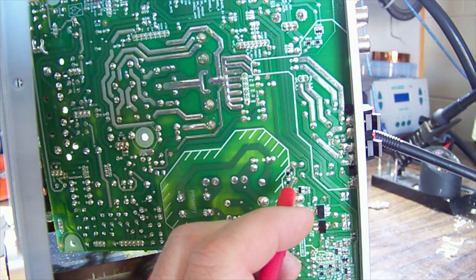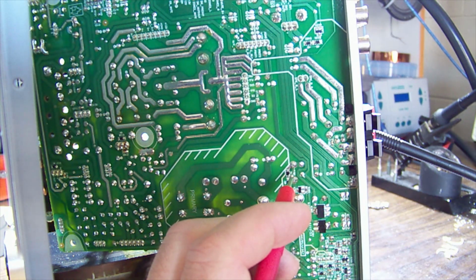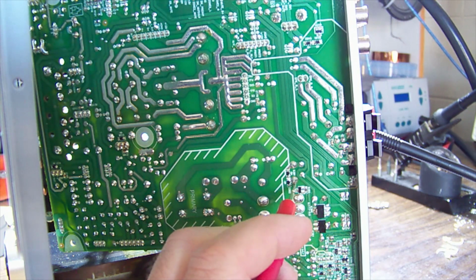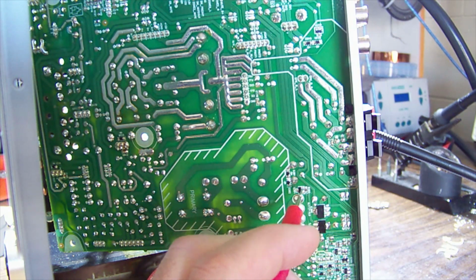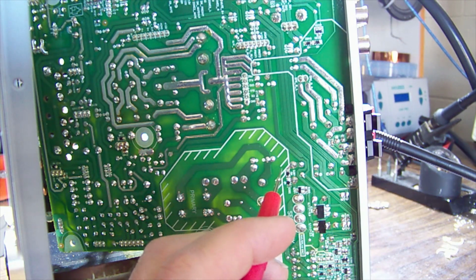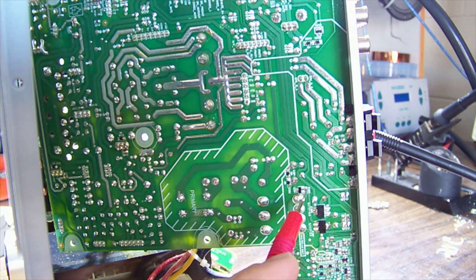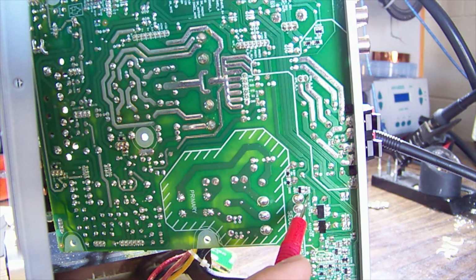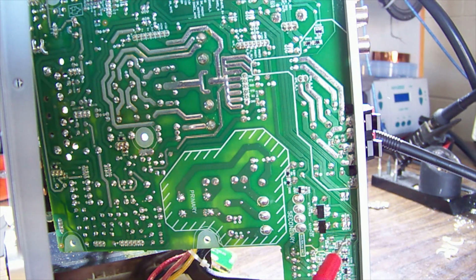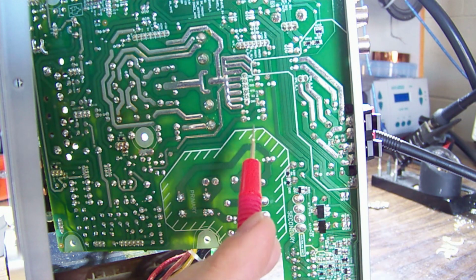So we'll go to our relay. We've got 10 volts there, and of course 10 volts there because it's not being pulled to ground by our control. And that control signal comes from, it says a resistor to ground across that, so it holds that in an off state. That runs all the way down here and back up to this resistor, which then runs all the way up to the processor.